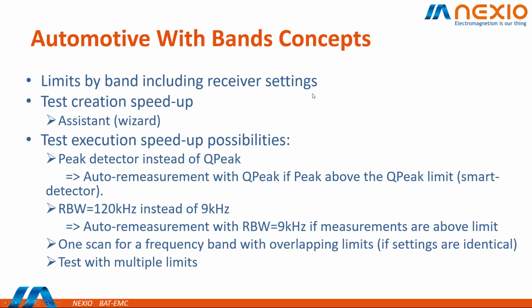So we have a limits by band including receiver settings, unlike the previous limits which were just a limit not to exceed. And this I will show in the next slides. With the test creation, it is much faster because of the wizard or the assistant. And we have other possibilities for speeding up the test. One, for example, is the peak detector instead of quasi-peak. If we use the peak detector, it is much faster.